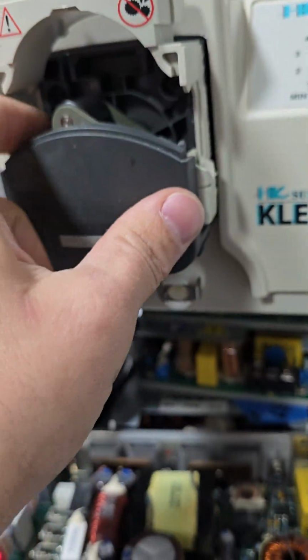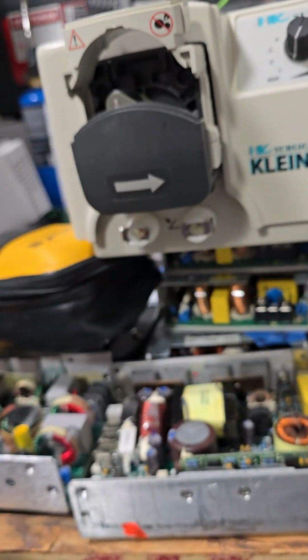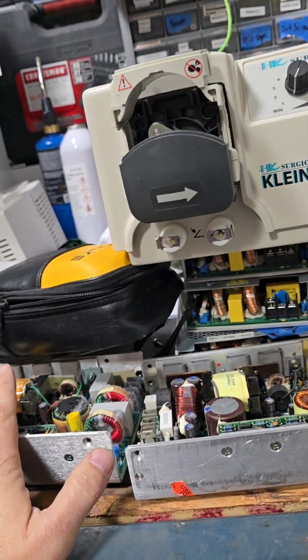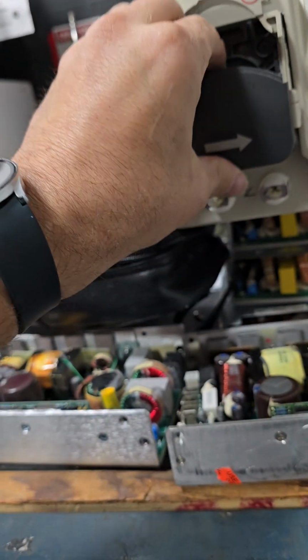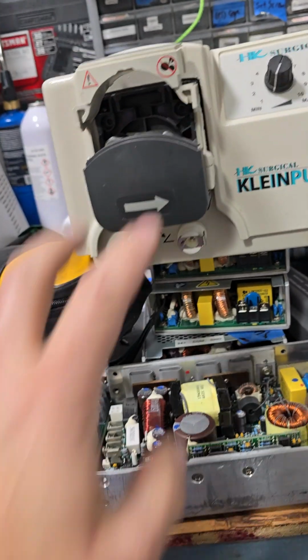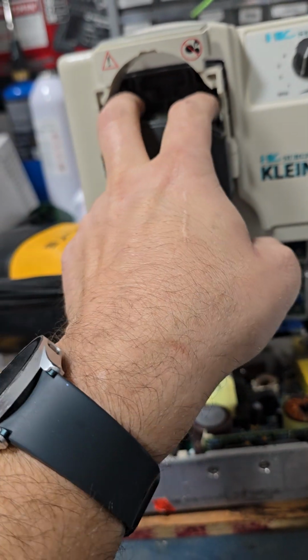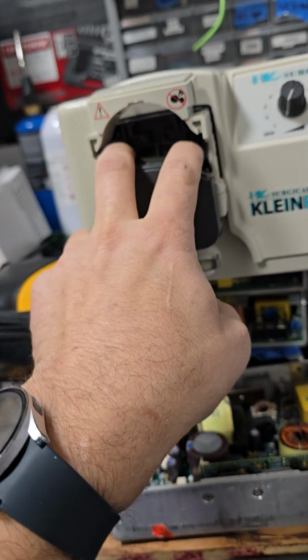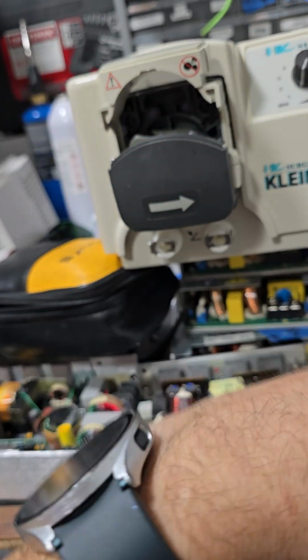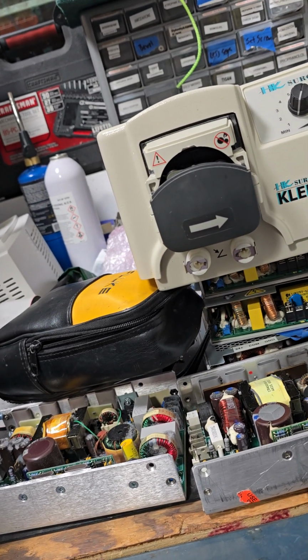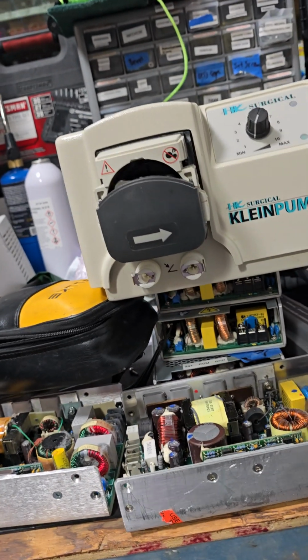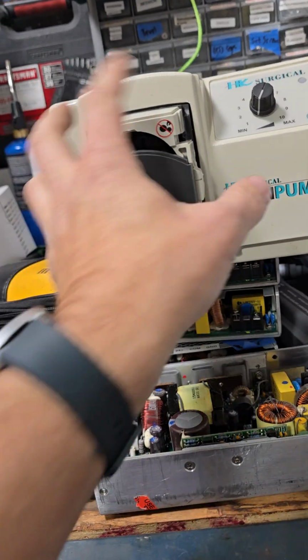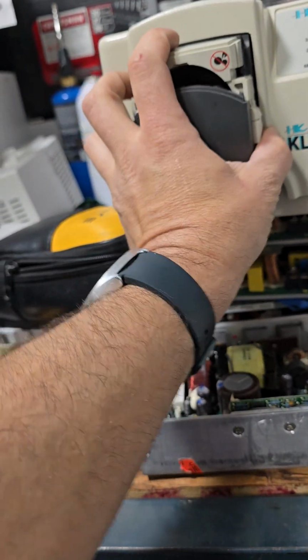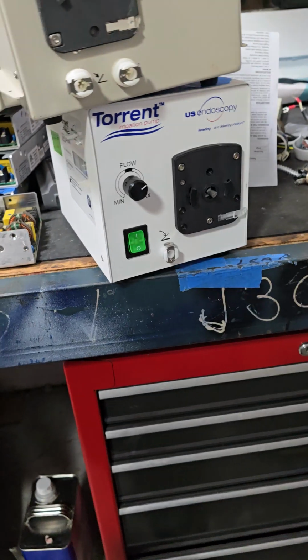This roller wheel moves, kind of massaging the fluid through, and that's how it controls the rate, based on the speed of the motor and the calculation that the engineers have done of the distance between here and here, so it knows how much it's pushing through the tubing off to wherever you're going. There's a ton of these different ones. Newer manufacturers are now making this built in so the pump head doesn't come off. But typically this thing just turns like 45 degrees clockwise to come off. And typically these things just spin off.